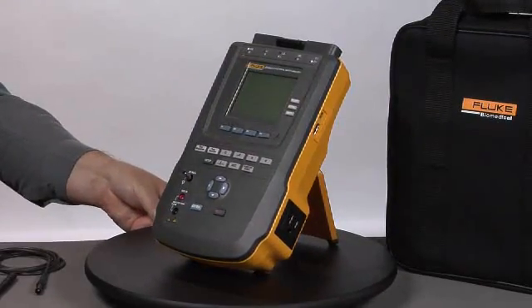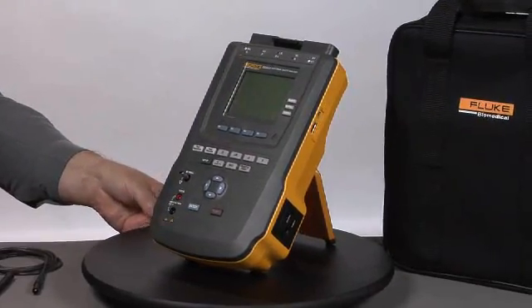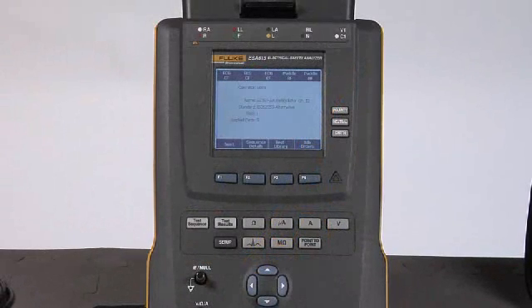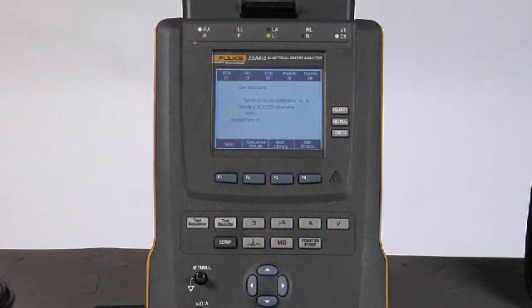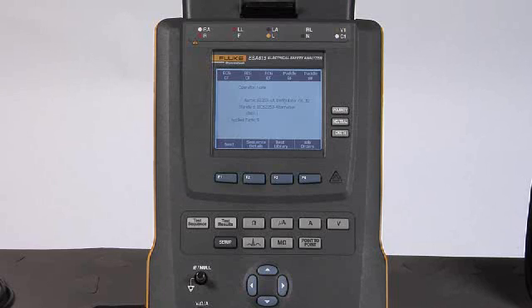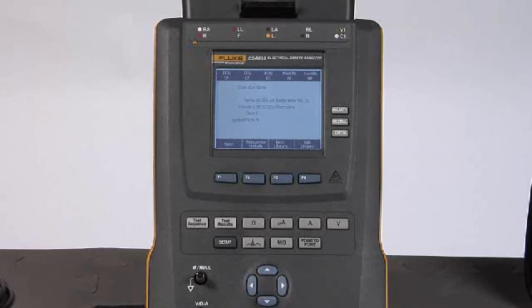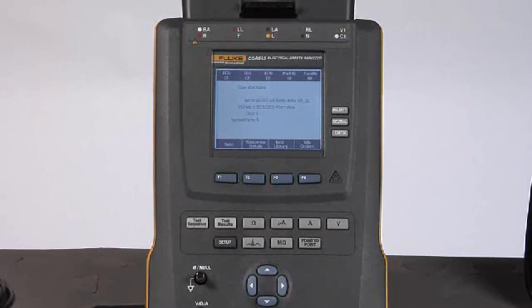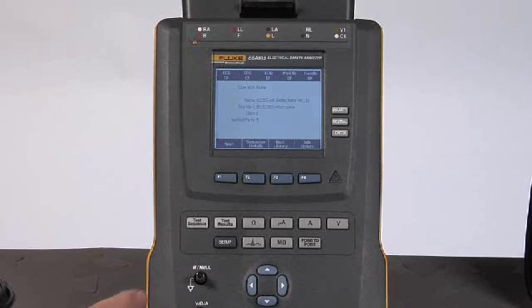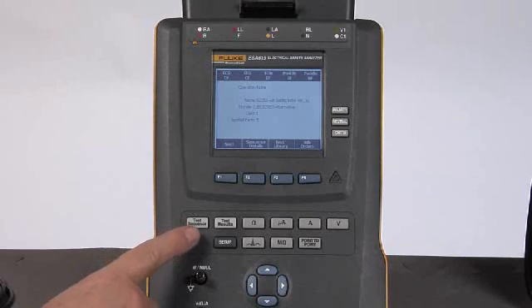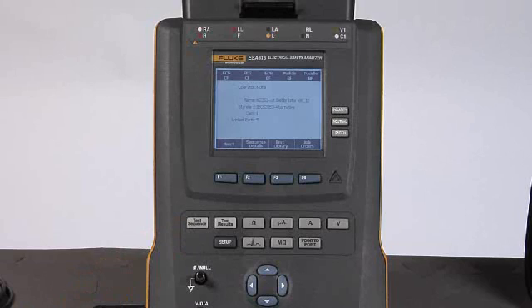Now we're ready to introduce the controls. Let's do a quick overview of the functions and features of the ESA615 automated electrical safety analyzer. To begin with, the unit defaults to the last auto sequence that I have just completed, so we would otherwise select the auto sequence button to get to the display you see on screen right now.